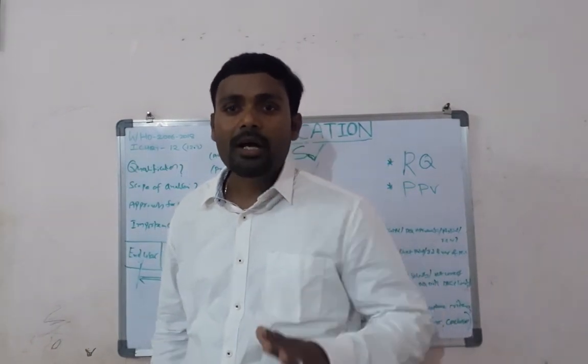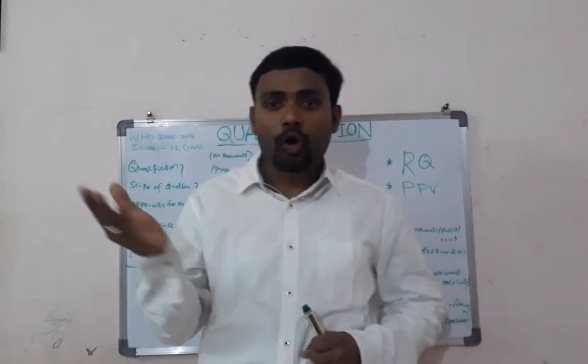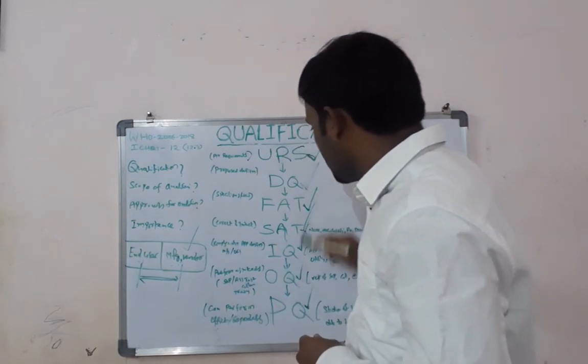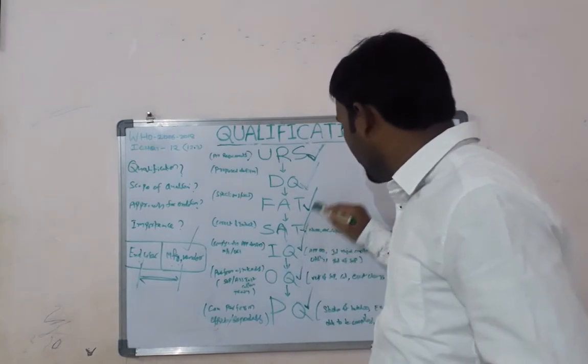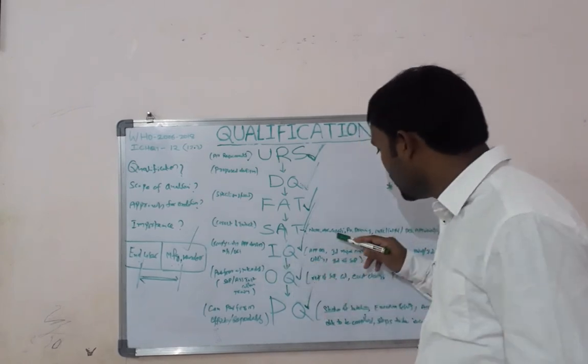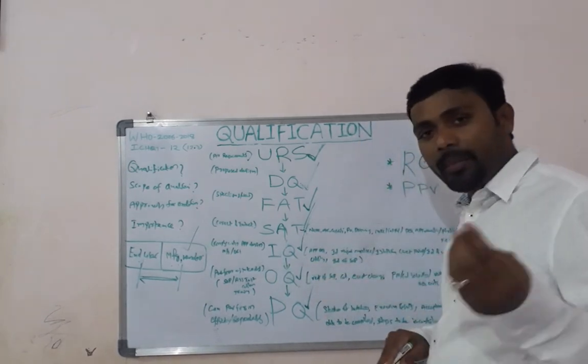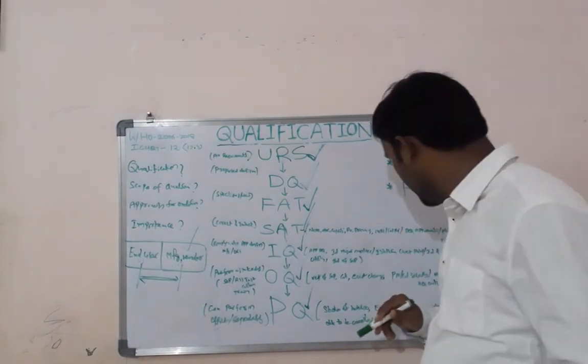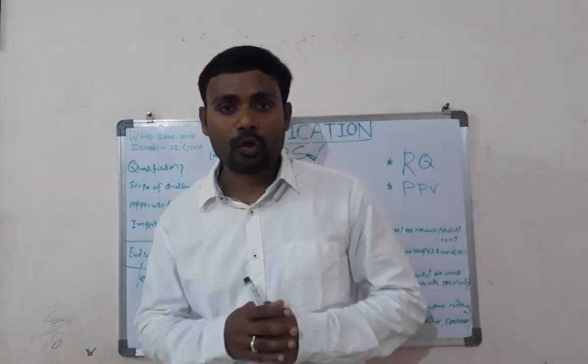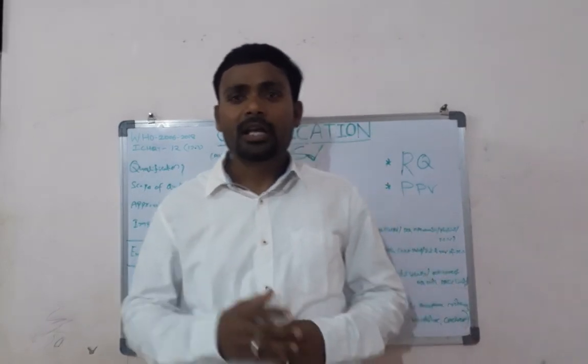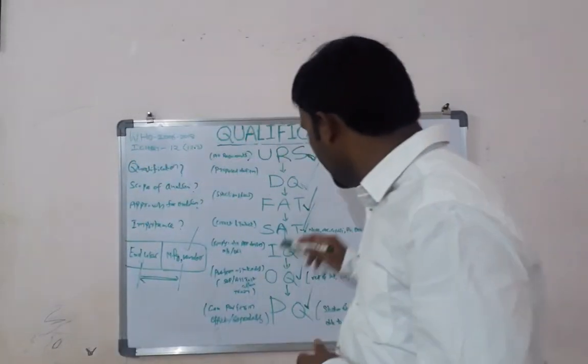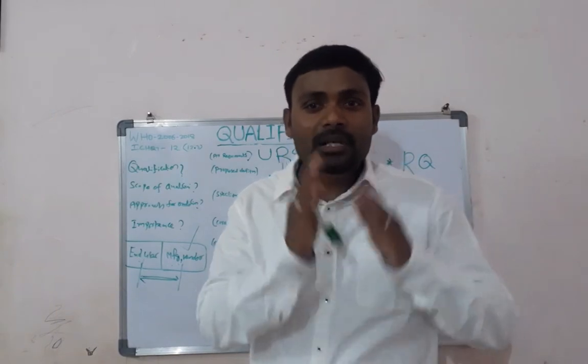Site Acceptance Test (SAT) is performed by the user to verify that the received equipment is in a controlled and intact condition. The SAT report must verify the equipment name, capacity, PO drawing, make and model, supply information, DQ approval verification, physical condition, and technical specifications. Any damage or part problems must be reported to the vendor for replacement.